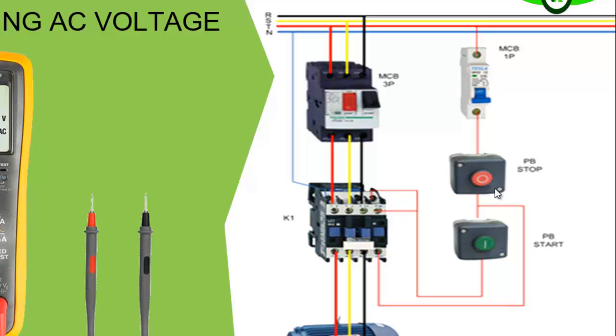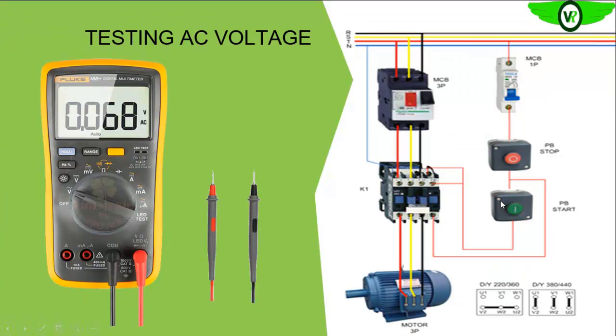When you depress it, of course you expect that the output of it should have signal. If there is none, that means that the start push button is faulty. Okay, and when you release, you are supposed not to have an output on the other end. Are you getting it? Because it is a normally open push button. So when you release, the contact is expected to open back. If you are not familiar with the switch operations and their symbology, check out our training on electrical diagrams. Okay, electrical diagrams and electrical component symbols, they are treated in that particular training.